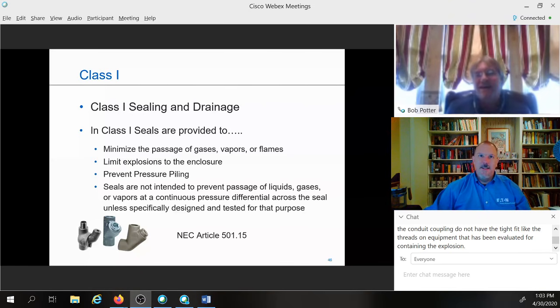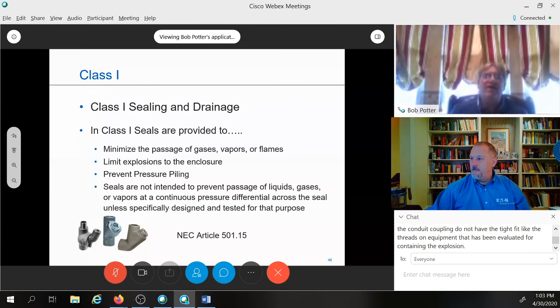Safety in numbers again. And this gets back to that 4 square that I just had on the screen that showed us when I have the Class 1 Division 2 area, and it's a non-arcing splice box, a terminal box, that particular piece of equipment is not required to be explosion proof. And that's where a lot of times in chemical plants, refineries, wastewater treatment plants, you may see regular everyday conduits or regular everyday junction boxes installed. And that's Article 501.10(B)(4).